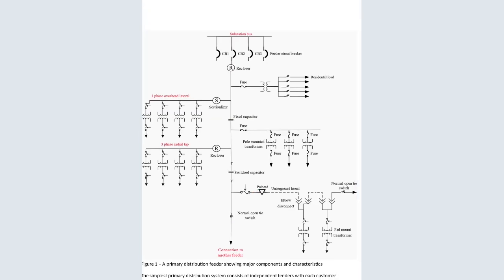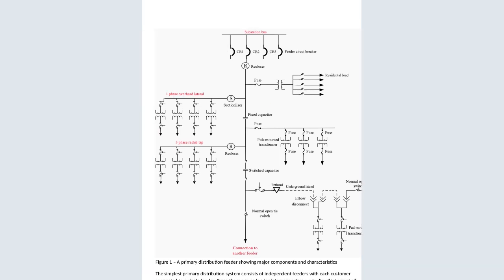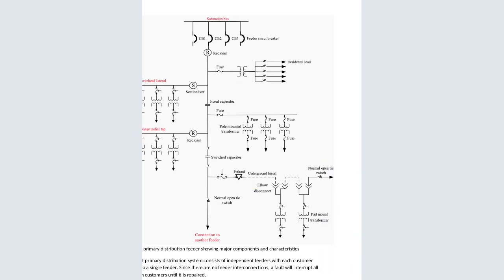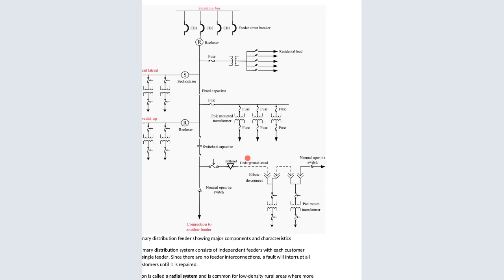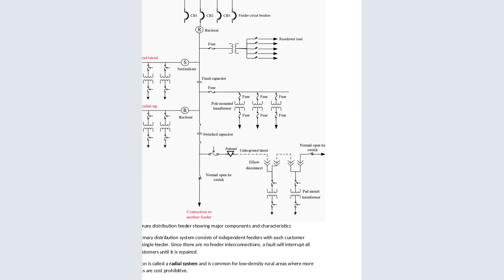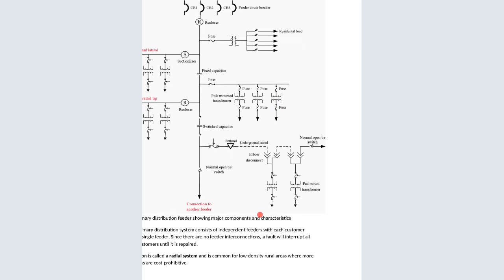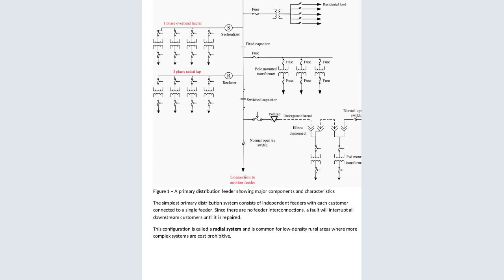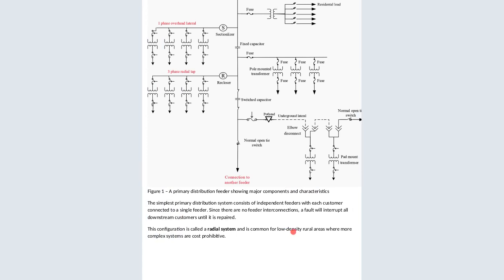So you can see this is a substation bus, the feeder circuit breaker, and then we have the 1 phase overhead lateral, and the phase 3 three-phase radial tap. This is a substation that is supplying different loads or different consumers. This one is another one that is a residential load. This is a fixed capacitor, a pole-mounted transformer is there, and another one is there for the normally open switch. Now this is called an elbow disconnect for an underground lateral. So you can see how the connection takes place. That is the connection to another feeder. So this is the primary distribution feeder showing major components and characteristics.